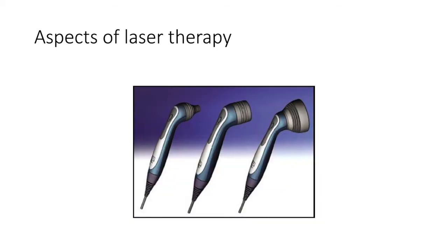So these are more or less different types of devices for laser therapy. Most LLLT apparatus generates light in the red visible and the infrared bands of the electromagnetic spectrum. The typical wavelengths of laser therapy range from 600 to 1000 nanometers. The mean power of these devices is generally low, from 1 to 100 milliwatts, though the peak power may be much higher than this. Sometimes it depends on the treatment, on what the doctor is treating.